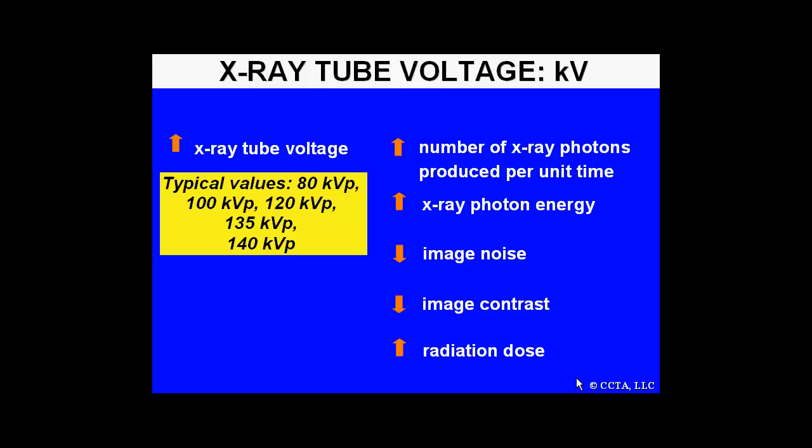The technologist sets up the scanner by first determining the x-ray tube voltage, KV or kilovolts. Typical values are 80, 100, 120, 135, and 140. Increasing the x-ray tube voltage will increase the number of x-ray photons produced per unit time and also increases x-ray photon energy. It does decrease image noise and decreases image contrast, but it also significantly increases radiation dose.